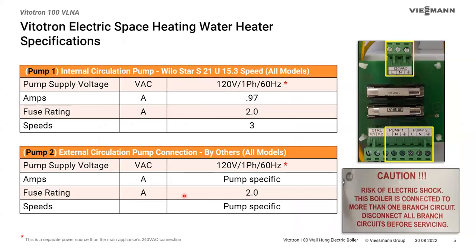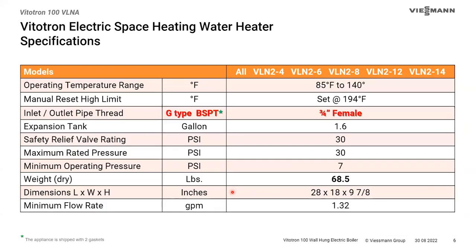The pump circuit is 120 volts. The internal pump is a Wilo Star three-speed pump at 0.97 full load amps, fused at 2 amps. The external pump would be similar — also fused at 2 amps, pump-specific. The maximum fuse rating on that circuit is 2 amps. The maximum operating temperature is 140°F, making this a low-temp boiler. People ask about domestic hot water — it's borderline; you might be able to do it through an indirect tank, but the maximum boiler temperature is 140°F.